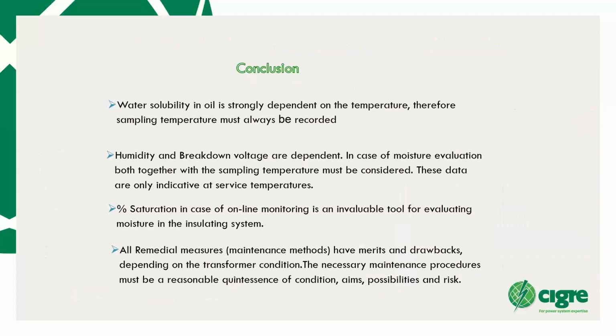So as a conclusion, I would like now to close my presentation here. Again, important things. Water solubility in oil is strongly dependent on the temperature, and that's why we should always record the sampling temperature. Humidity and breakdown voltage are interdependent, and they must both be considered when evaluating moisture. And this is indicative only at service temperatures, because at low temperatures the whole water is again in the solid insulation, and in oil you cannot see anything.